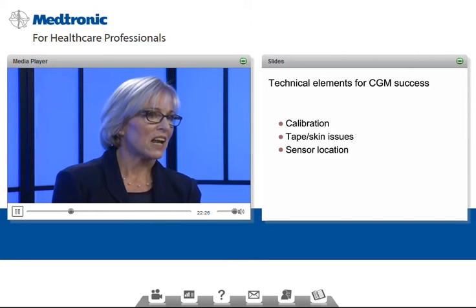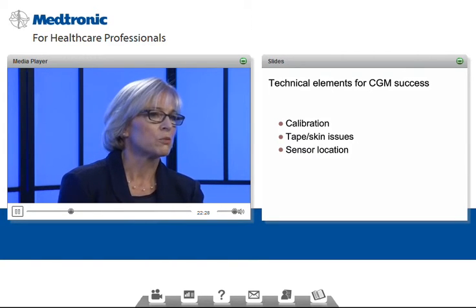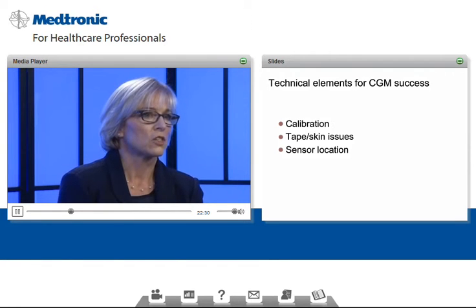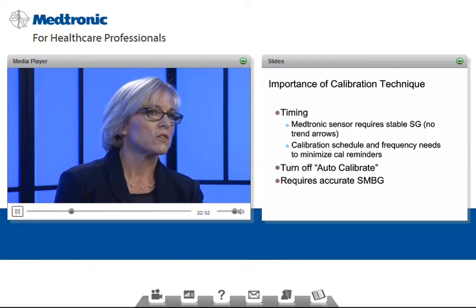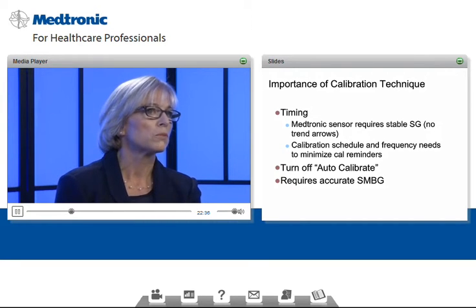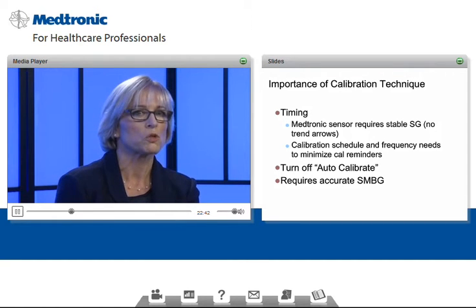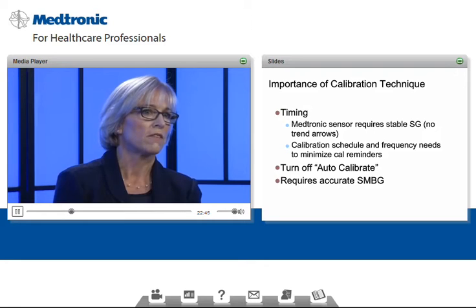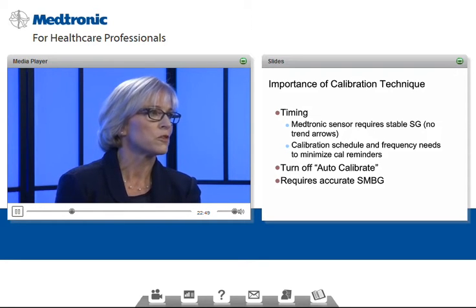So going back to the elements for success, there are some technical ones which are really key, as with any technology. Calibration is very important. It can be a challenge for families if they're not instructed and supported in proper calibration technique. Timing is very critical with the Medtronic sensor. It does require stable sensor glucose, which means no trend arrows at the time of calibrating. And the calibration schedule and frequency needs to minimize cal reminders if people get annoyed and frustrated with the device. So setting that up for success is really important.